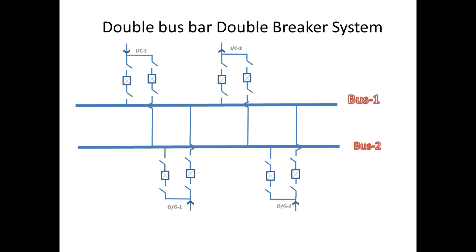We can connect any feeder to any bus, but before closing the breaker, the related two isolators have to be closed first.